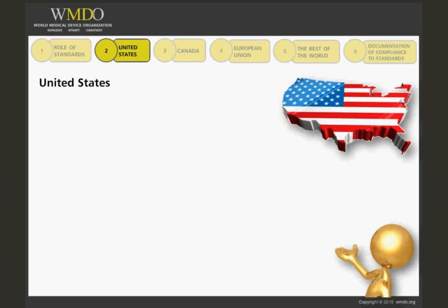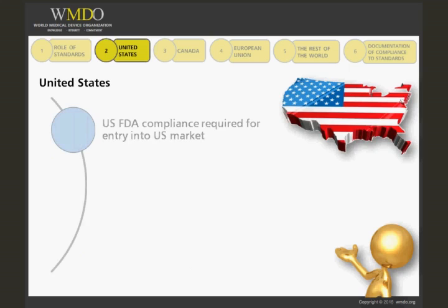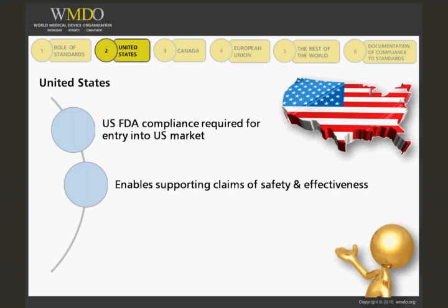In the United States, you must meet the FDA requirements to place a medical device on the U.S. market. The medical devices must be safe and effective to meet the requirements of the Federal Food, Drug, and Cosmetic Act. Using FDA consensus standards enables supporting the claims of safety and effectiveness.